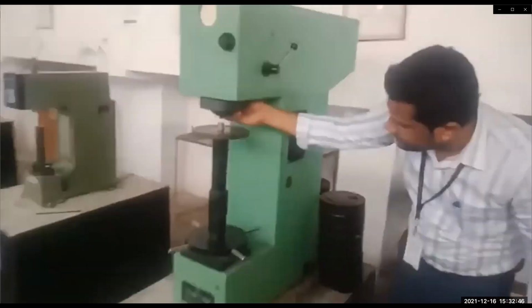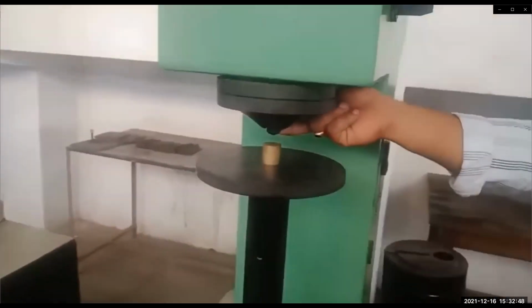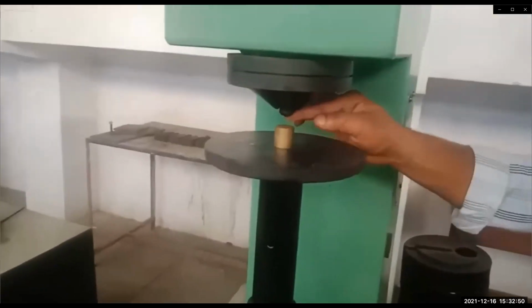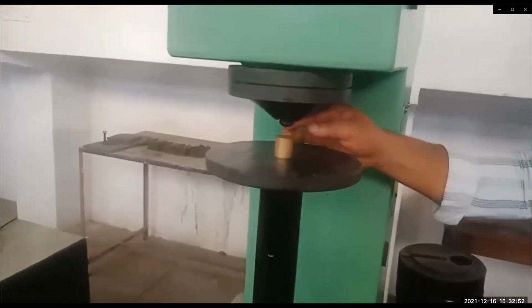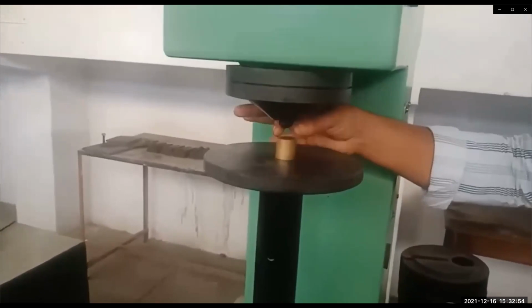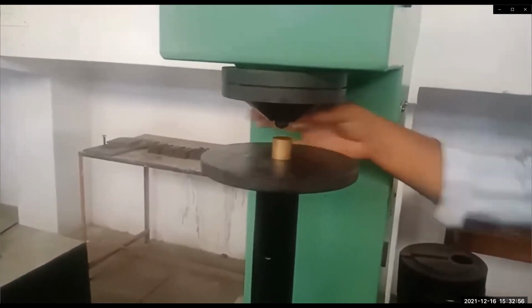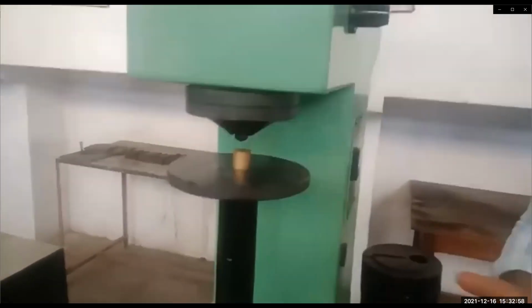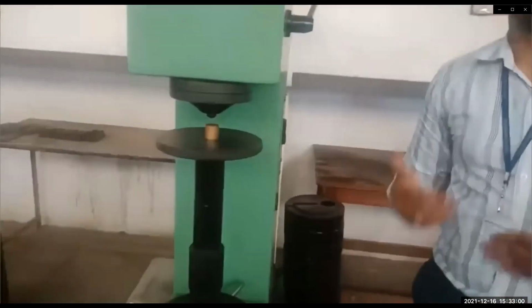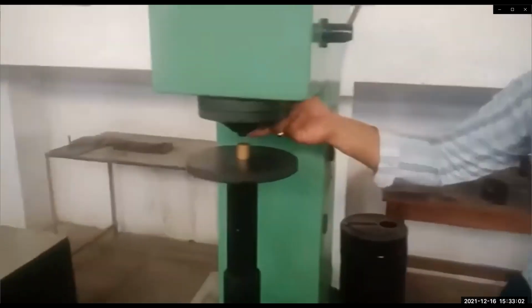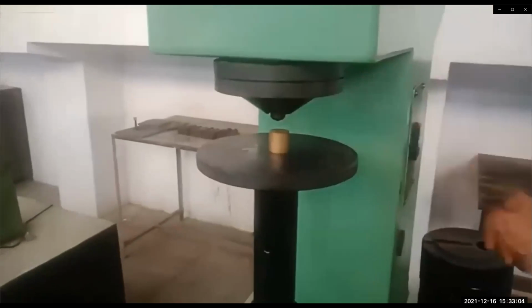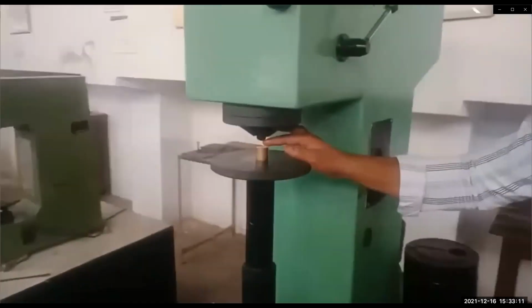This is the indenter we are fixing, with the indenter knob, that is the indenter holder. The indenter we are using is a steel or carbide steel ball indenter. The diameter is 10 mm. For different diameter balls we use different loads, but now we are using the 10 mm ball. That is the load we are applying, 1000 kg with the help of the weight pan. Then the effective load is transferred to the indenter.